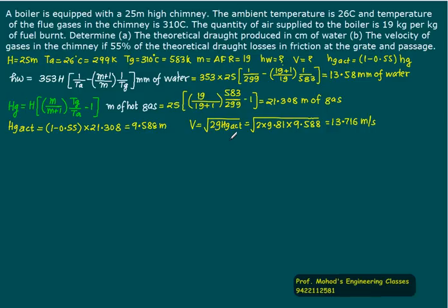Velocity is given by √(2g×h) in the column of hot gases. So √(2 × 9.81 × 9.588) gives velocity of hot gases as 13.716 meters per second.